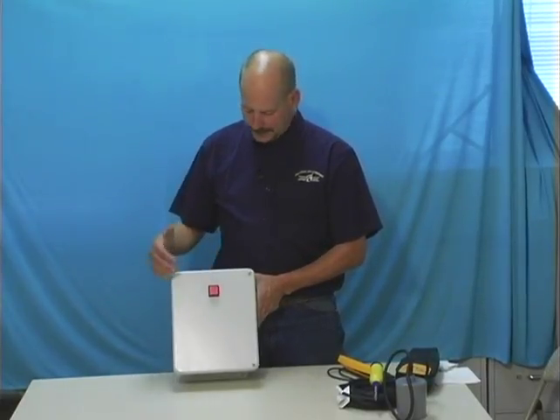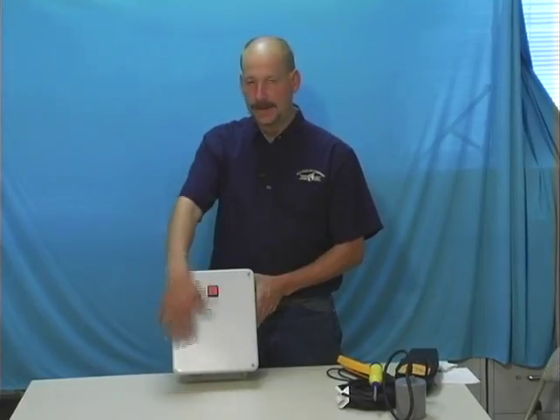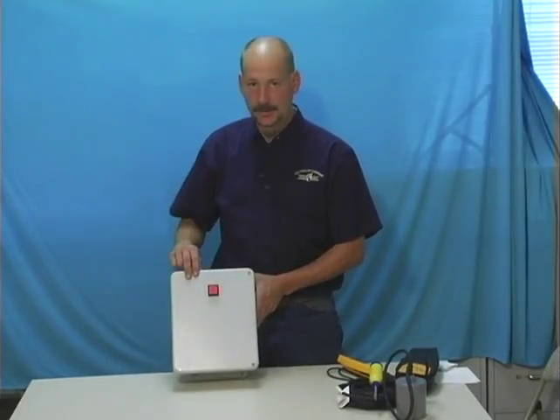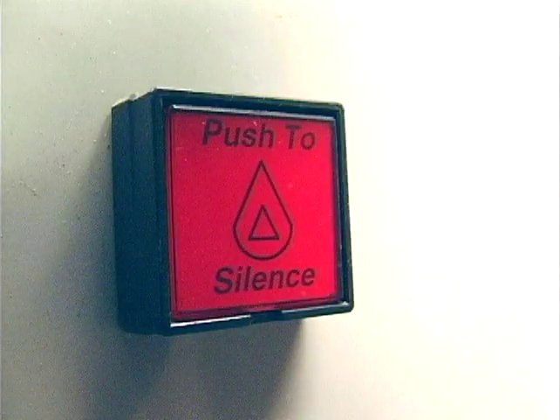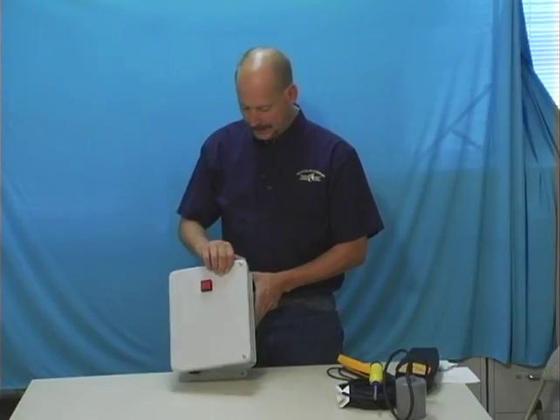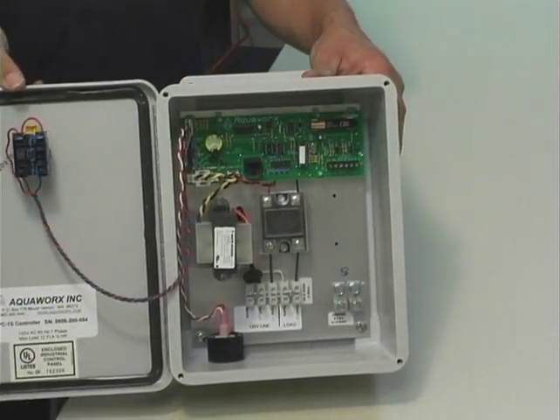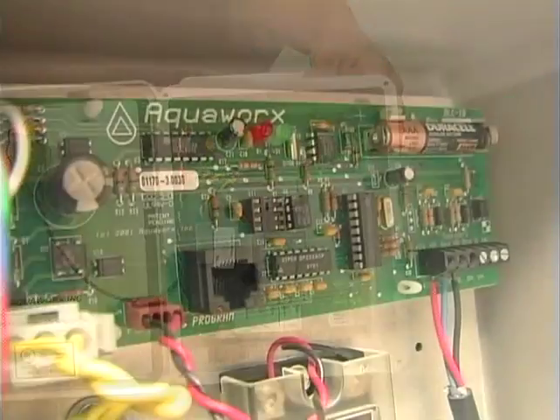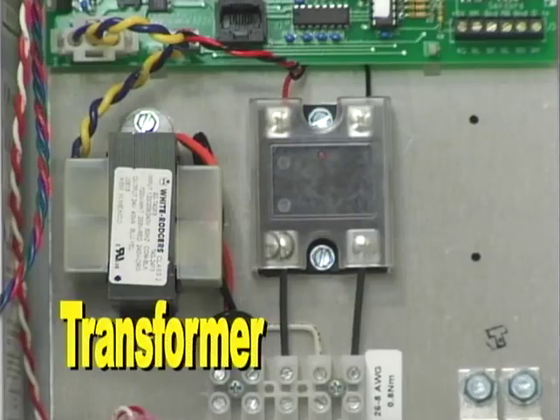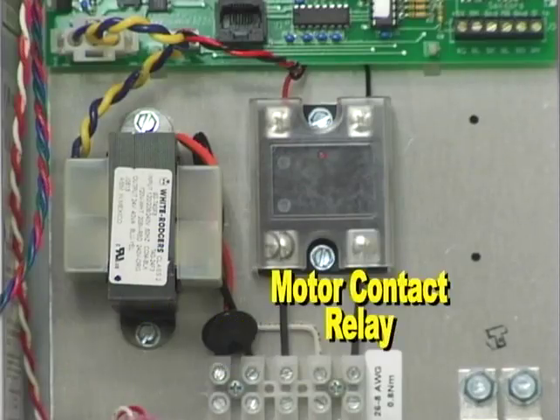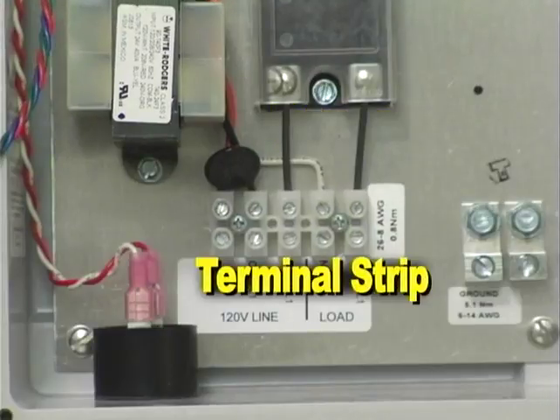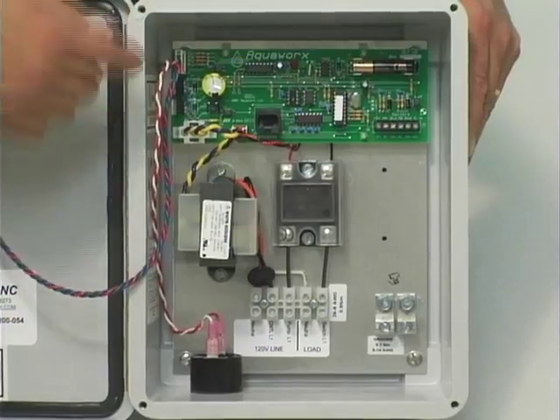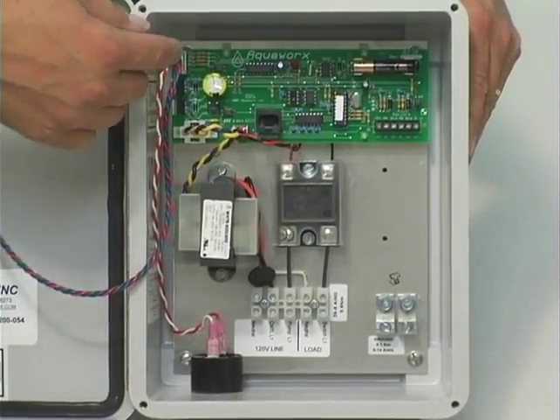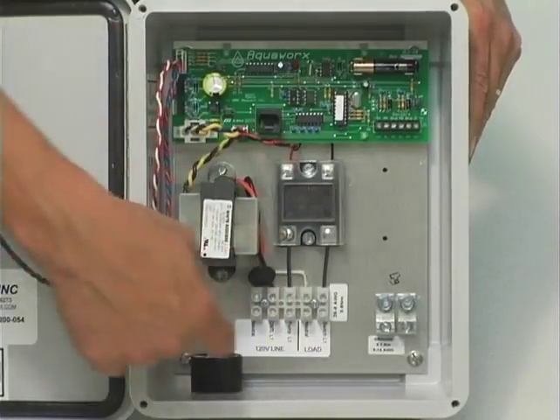The next control panel, or another one of the control panels that we carry, is the Aquaworx control panel. There's no identifiable markings on the outside of the control panel except the small Aquaworx logo in the center of the push to silence button. This too is not like the Orencos or the Rhombus panels when you open it up inside. The only thing you have in here is a printed circuit board, a transformer, a motor contactor, and a terminal strip. If you'll notice on the internals of this control panel, there is no hand-off automatic switch.